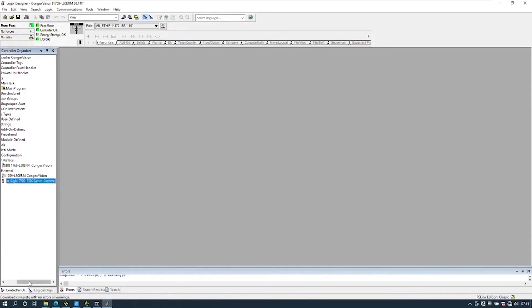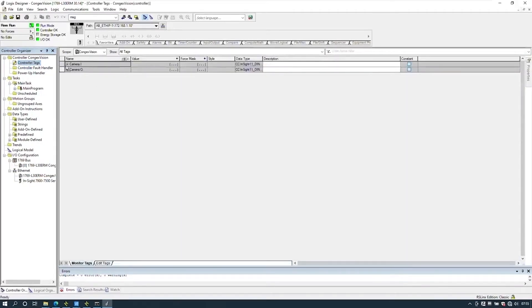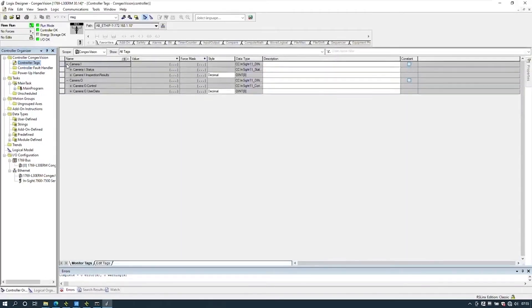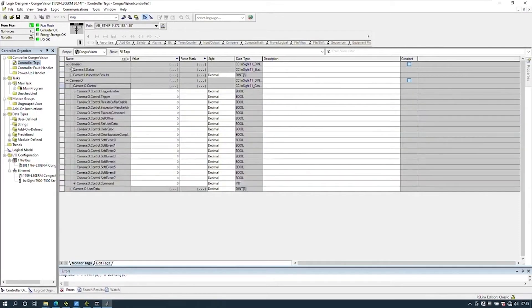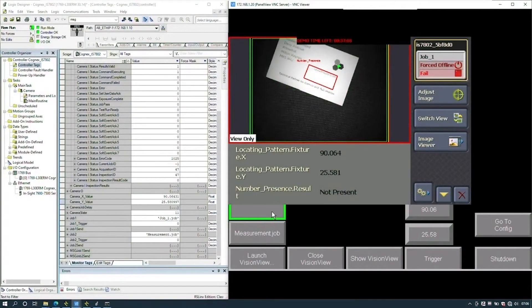The IO light is solid, there are no faults on the camera, and the Ethernet tree is working. Let's go look at the data in the controller tags — the control data to the camera and the status data from the camera. Now we'll look at triggering a job change in the camera by pressing an HMI button. Press the Job One button — it goes offline for a moment and then is changed.